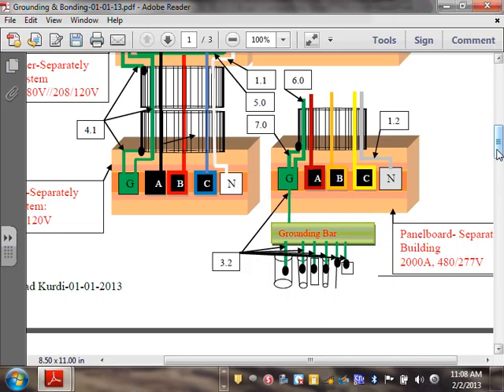I don't know why you say separately derived system. The only time you use the term separately derived system is if you have a generator, another transformer, a UPS system, or a photovoltaic system. If you feed another building from the same voltage, that's not a separately derived system. Can I feed the second building from a separately derived system? Yeah, I can throw in a transformer, indoor or outdoor, and transform the voltage to 208/120 and feed the second building. Then that changes the game slightly, and that puts us into separately derived system bonding and grounding, which I'm going to talk about in a second.